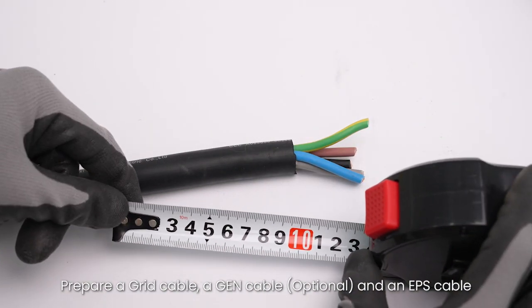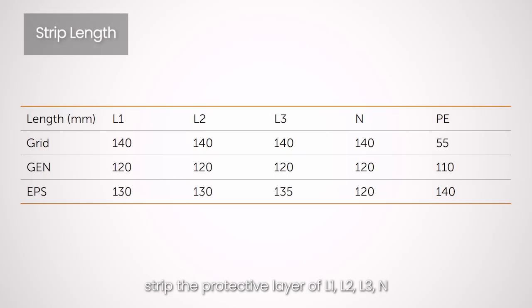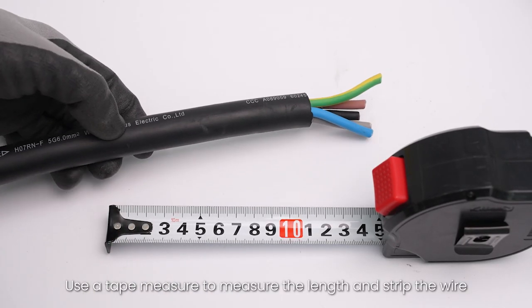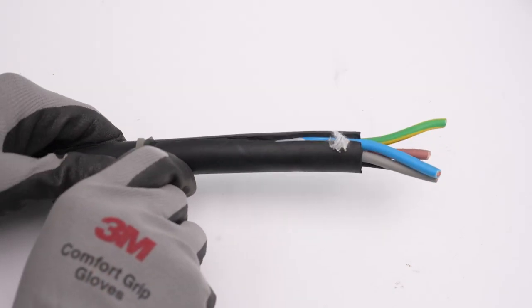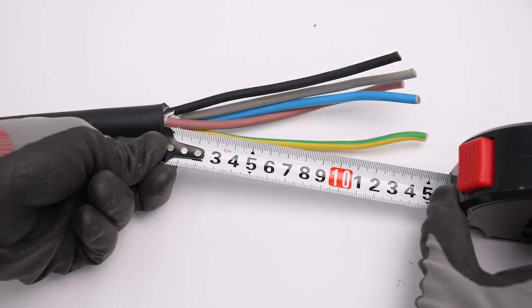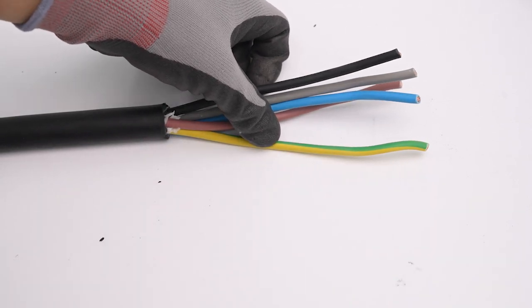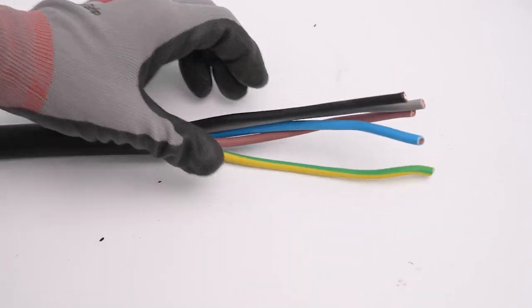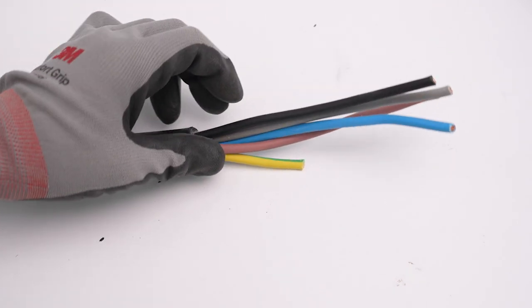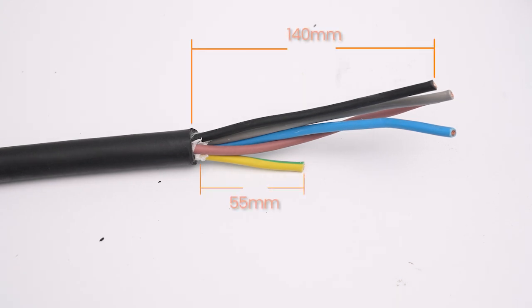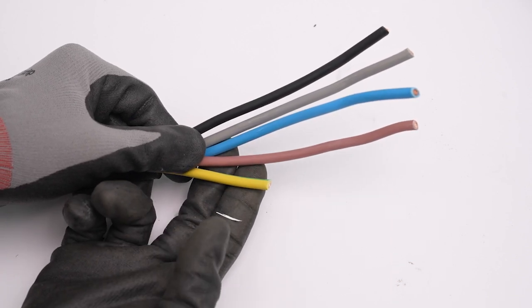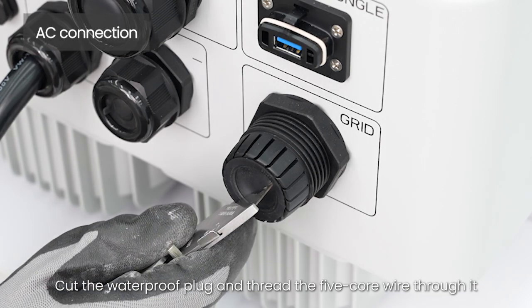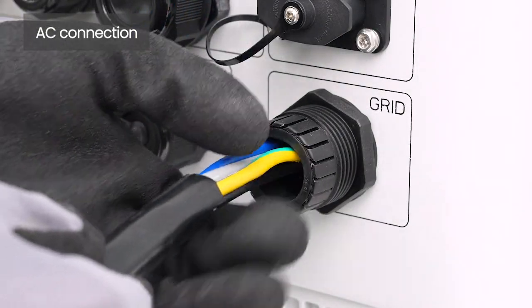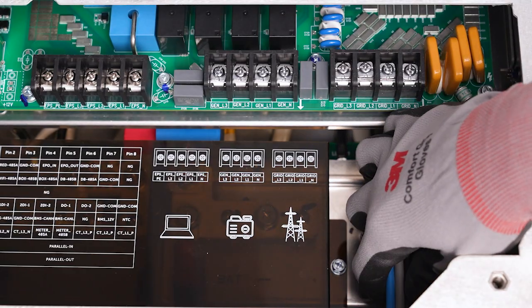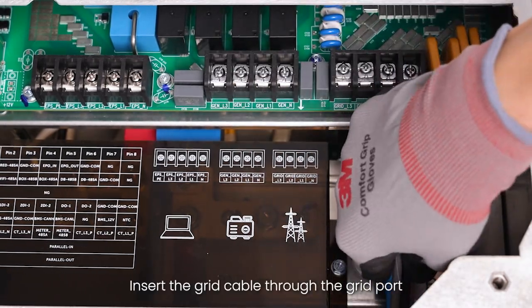Prepare a grid cable, a generator cable, and an EPS cable. Strip the protective layer of L1, L2, L3, N, and the grounding conductor according to the recommended length in the table. Let's take the grid wire as an example. Use a tape measure to measure the length and strip the wire. Cut the waterproof plug and thread the 5-core wire through it. Insert the grid cable through the grid port.